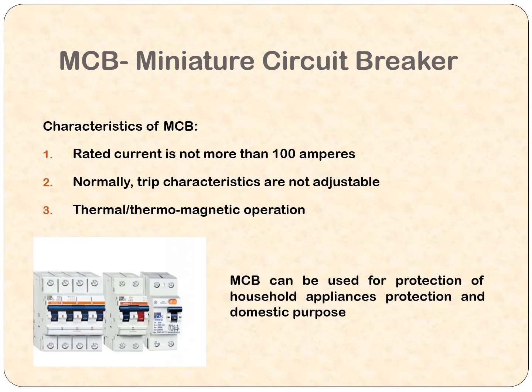The characteristics of the MCB are that it can be used up to 100 amps, which means the rating as well as the product can support 100 amps flowing through it. Normally the trip characteristics are not adjustable. That is, once the manufacturer fixes the rating, you can't make any adjustments to it. It has thermal and thermomagnetic operations, which means if abnormal temperature is sensed by this MCB, it will take action, and of course for overcurrent it will happen. Overcurrent makes the circuit heat up and causes fire. Before that, your MCB has to protect your home appliances and your operators.